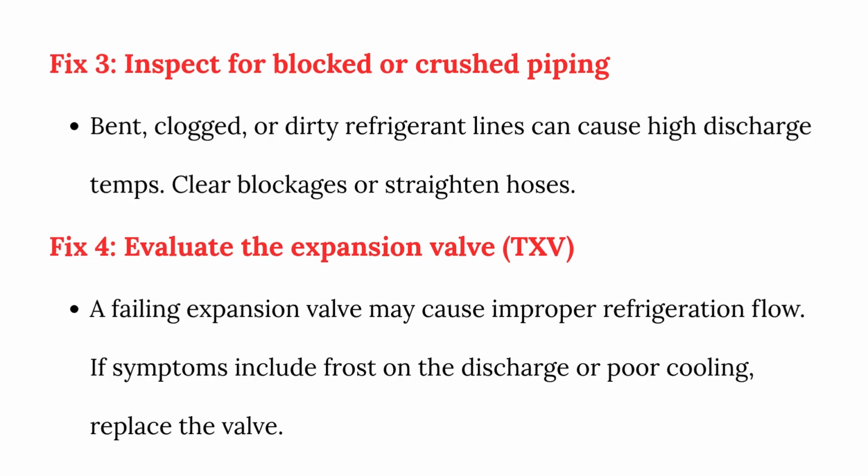Fix 3. Inspect for blocked or crushed piping. Bent, clogged, or dirty refrigerant lines can cause high discharge temps. Clear blockages or straighten the lines.